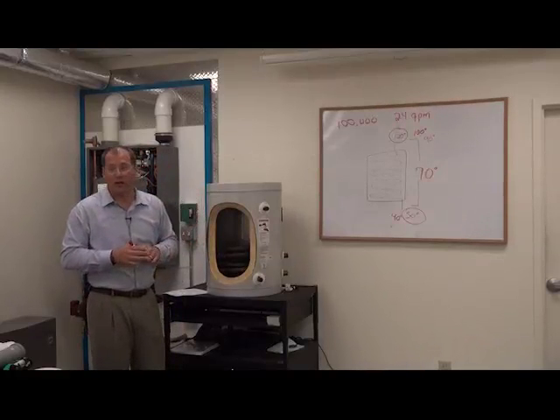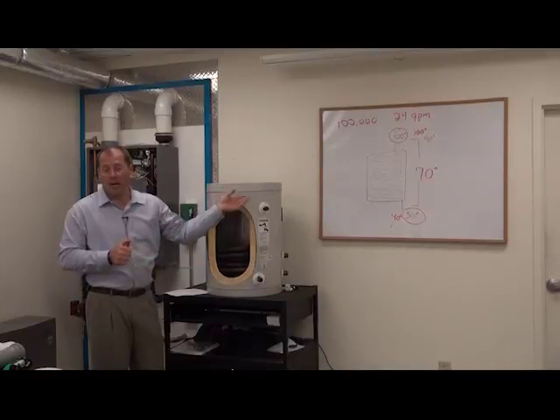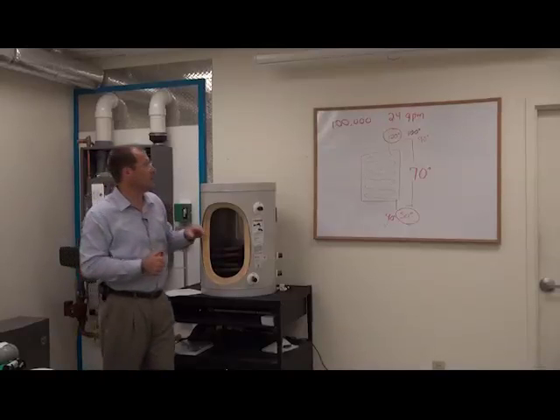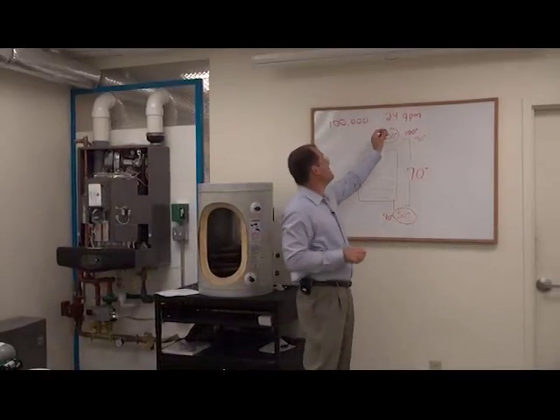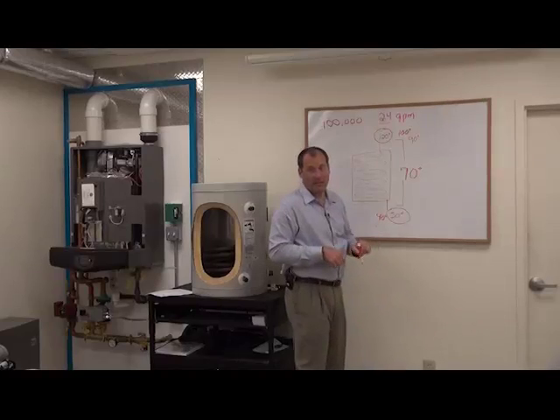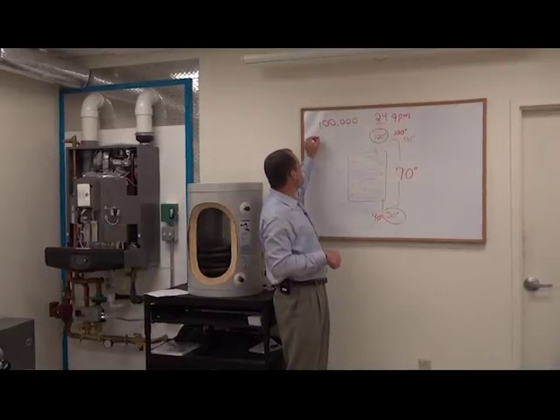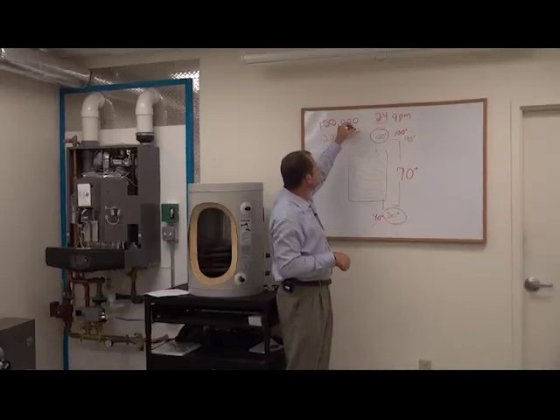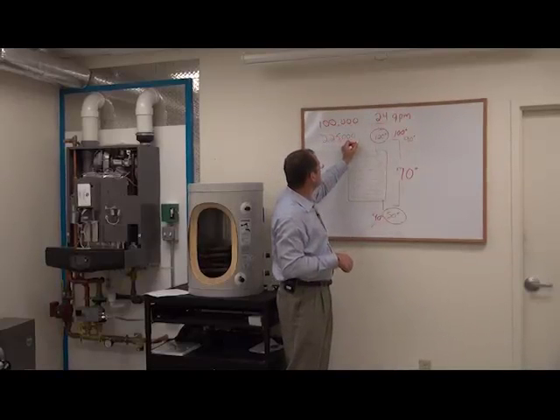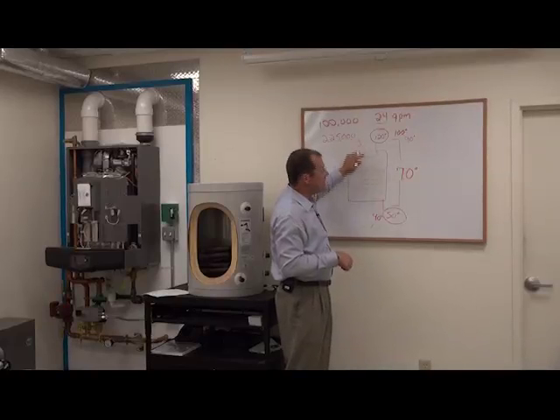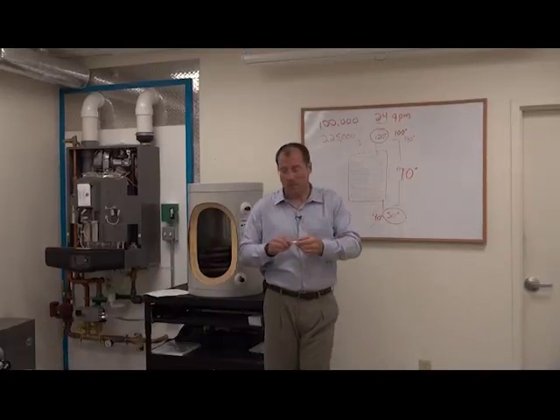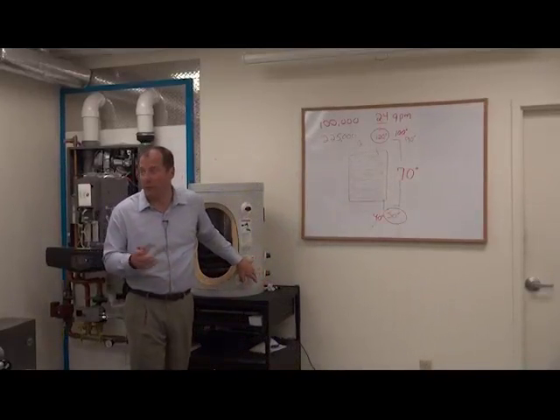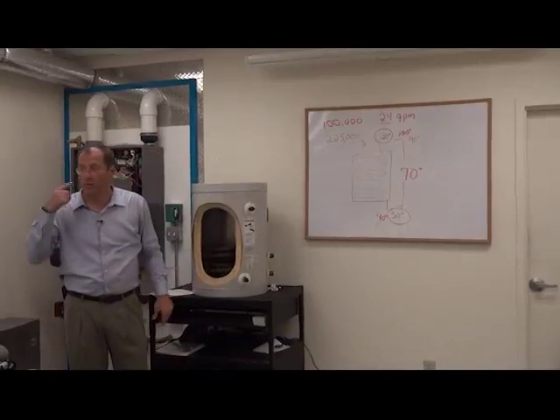You just have to make sure that you don't put that in an application where you need to fill up your jacuzzi tub at 5 or 10 gallons a minute, and you only have this. Because then what ends up happening is you need this to be much bigger. It might need to be 225,000 BTUs to give you 6 gallons a minute. So that's a consideration. Anyone that might have a vacation home that does not want to have this tank warming up and cooling down and warming up and cooling down, that's a nice way to go.